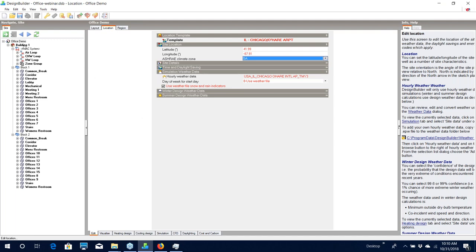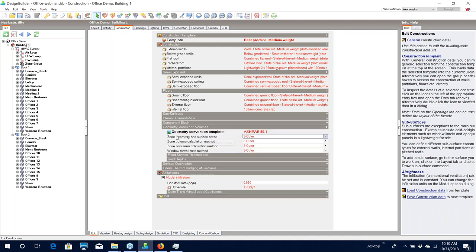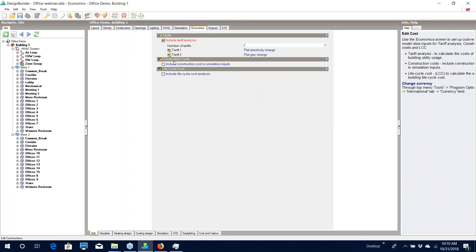If we go to building level and look at the Construction tab, we should check that the geometry convention template is set to ASHRAE 90.1. In Design Builder when you draw your geometry you use lines to represent the walls, but in actuality the walls have a thickness, and how that thickness is applied based on the position of the lines can change the floor area and zone volumes. By selecting the ASHRAE 90.1 convention, the zone areas and volumes should be the same between the proposed and baseline buildings even if your wall thicknesses are different. Because a LEED analysis involves both energy and cost, you should also include a tariff in the economics analysis so the cost of electricity and gas can be applied correctly.